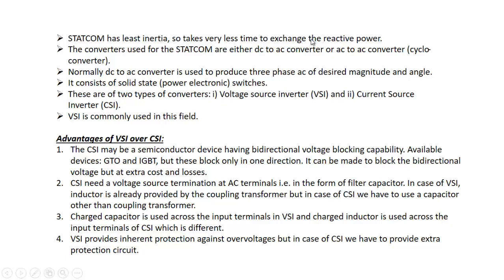STATCOM takes less time to exchange power. The converters used for STATCOM are either DC to AC converters or AC to AC converters. If DC to AC converters are used, they are usually inverters. AC to AC converters can be AC voltage converters, AC voltage regulators, or cyclo-converters. Normally a DC to AC converter — that is, the inverter — is used to produce three-phase AC of desired magnitude and angle.